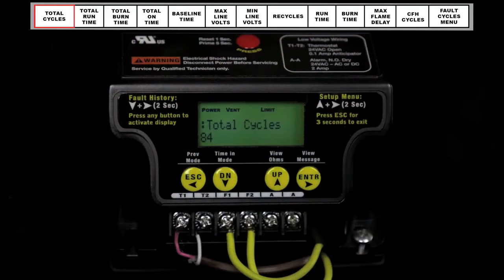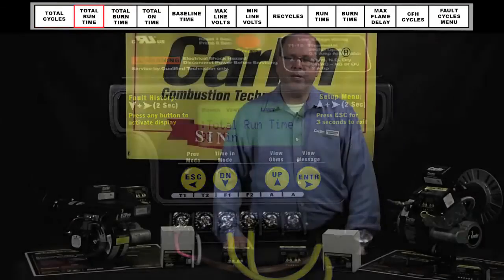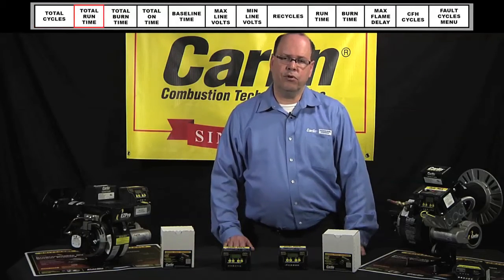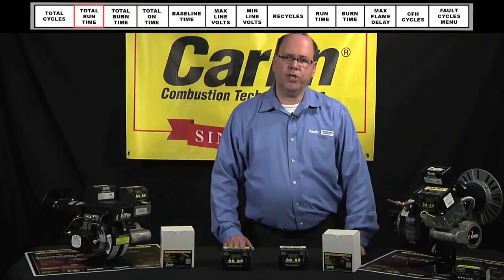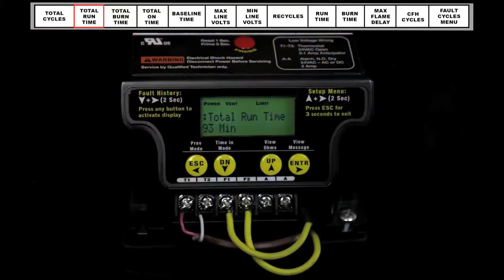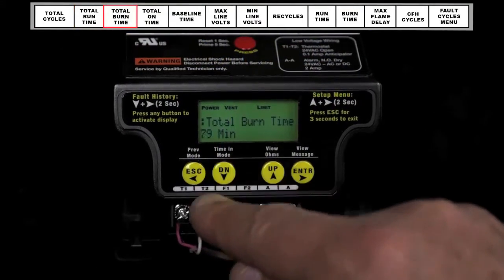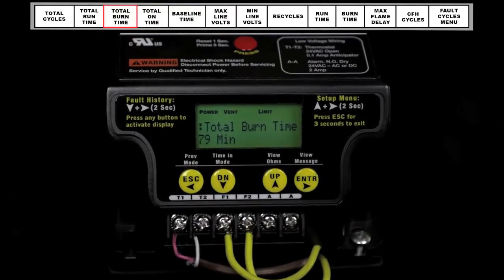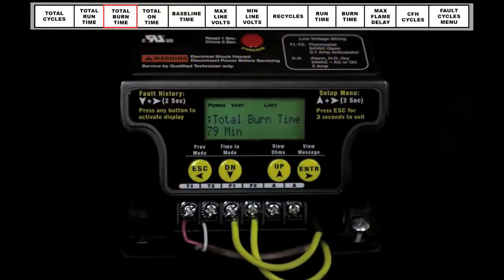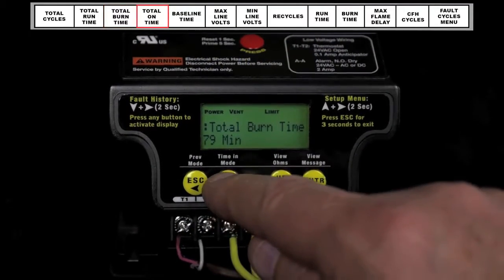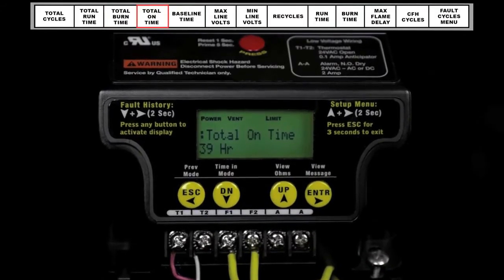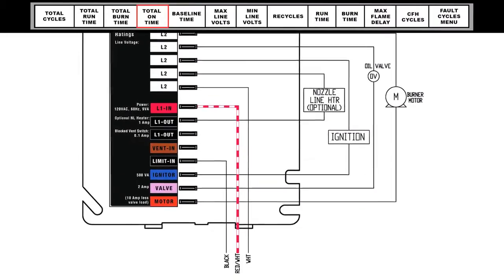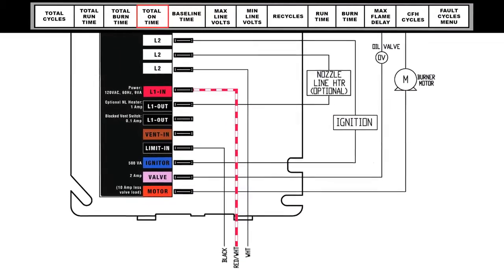Press the down arrow to get total runtime. Total runtime is a measurement of how long the burner has run, including pre-purge and post-purge times. Pressing the down arrow next to get to burn time. Total burn time indicates when a flame should be present. Press down arrow again. Total on time is how long the control has been powered. This feature is measured at the power lug red-white wire.